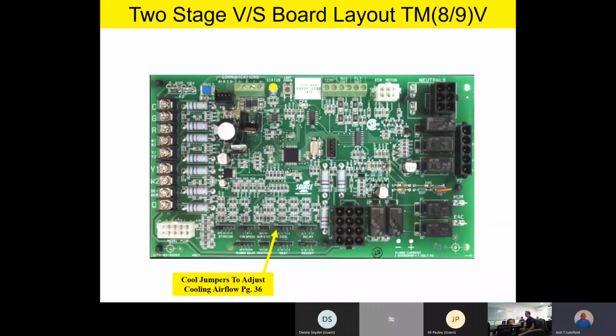So if you have your cool and your adjust jumper set up for, in my example, 2.5 tons, 1,000 CFM, and you have a Y1 call on the board all by itself, a Y1 call for first stage cooling, it'll automatically run the fan at 650 CFM. And then when I get a Y2 call, the fan will ramp up to 1,000 CFM in my example. So please keep that in mind. When you set up your cool and your adjust jumper, you're always setting that up for your Y2 or high speed second stage cooling call.